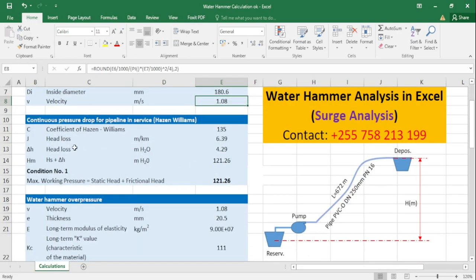Now the continuous pressure drop along the pipe, using Hazen-Williams, where C for Hazen-Williams is 135, which I picked. Then head loss in meters per kilometer, that one. Then head loss in meters of water column, which is going to be 4.29.